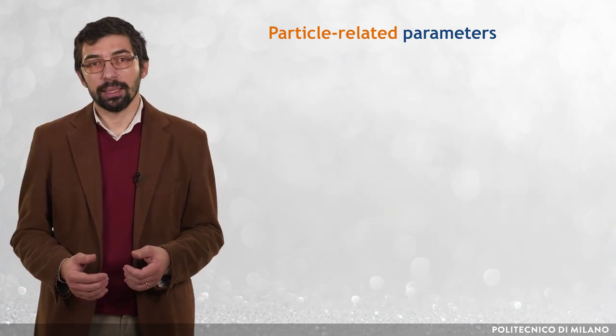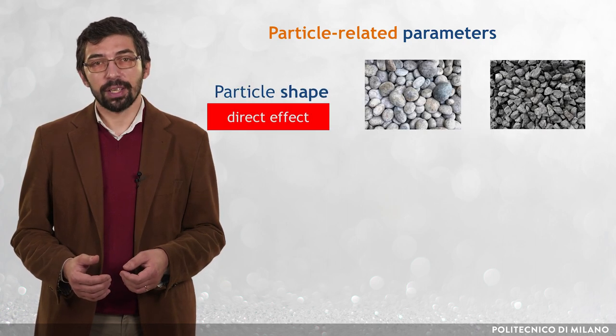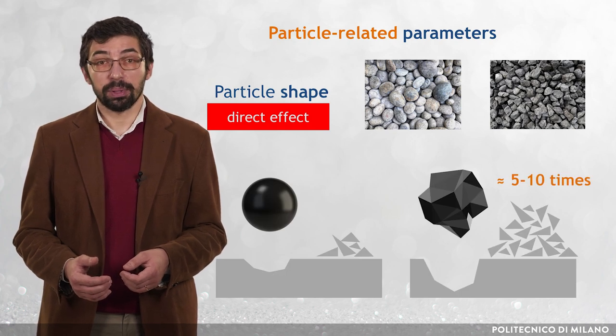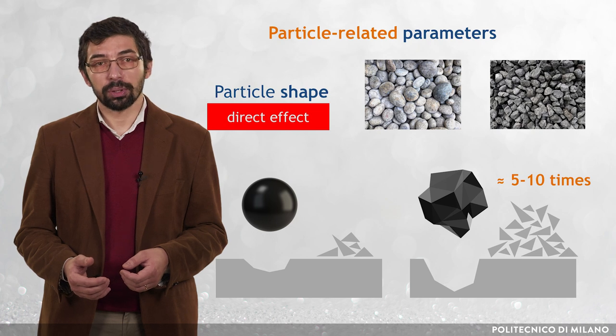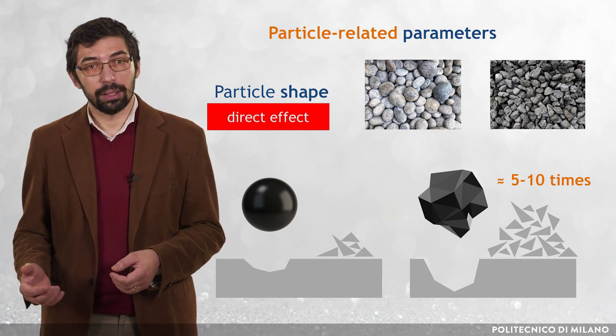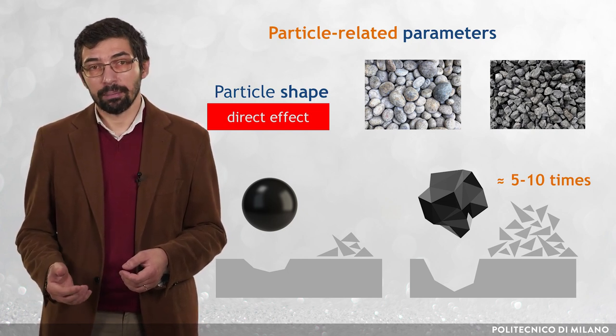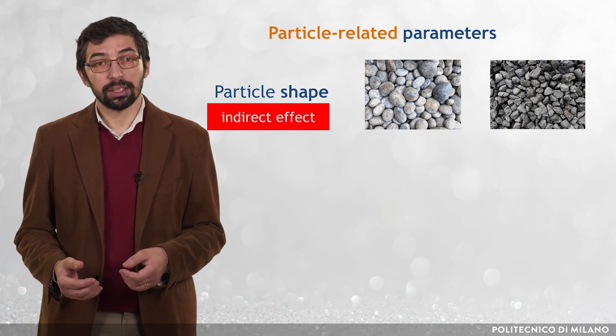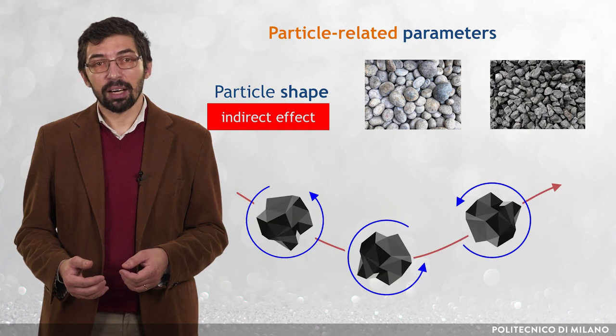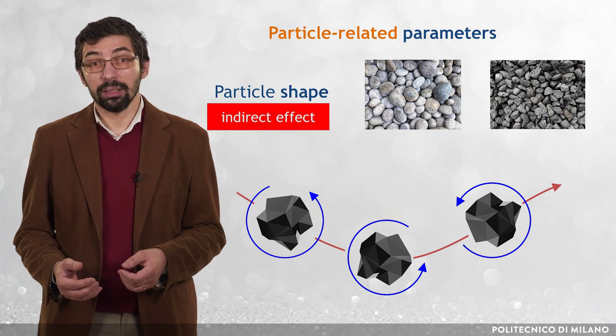Two other particle-related parameters are particle shape and particle material. The direct effect of particle shape on erosion was found significant by many experimenters, who observed that the erosion potential of an angular particle could be as much as five to ten times higher than that of spherical particles with the same material and size. In addition, the indirect effect has to be considered, since the shape of the travelling particle affects its trajectory through, for instance, a change in the drag coefficient or an induced spin.